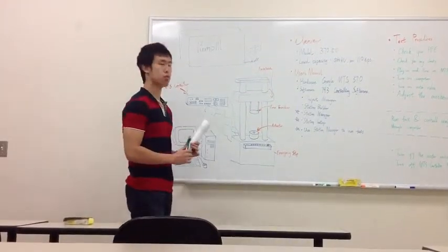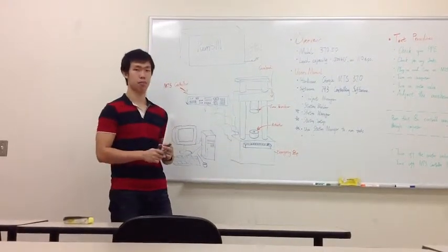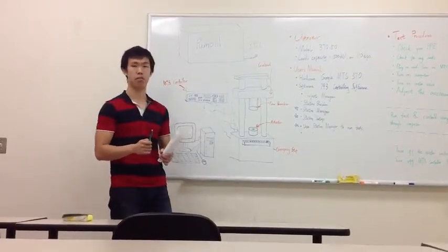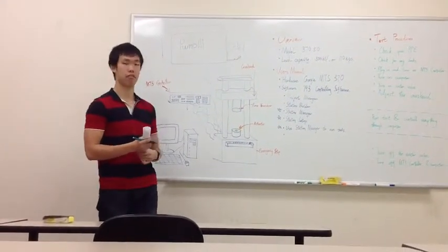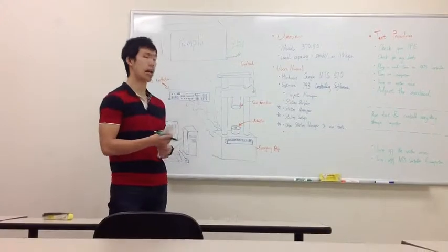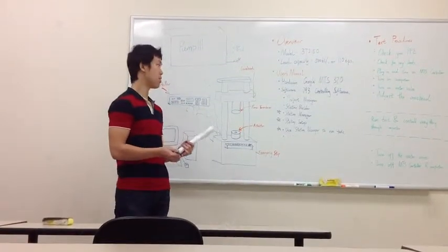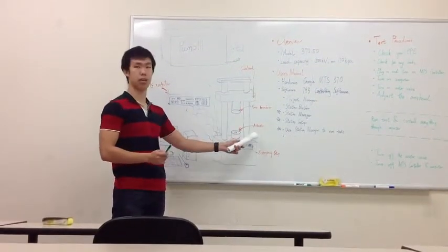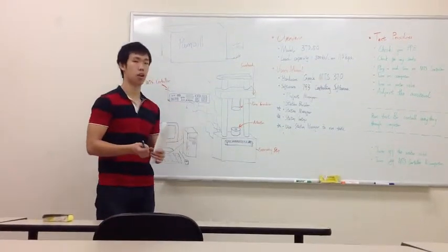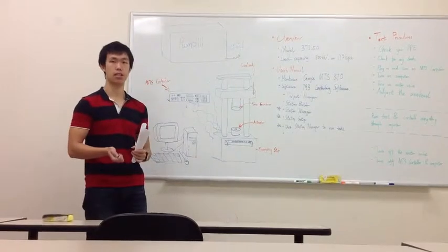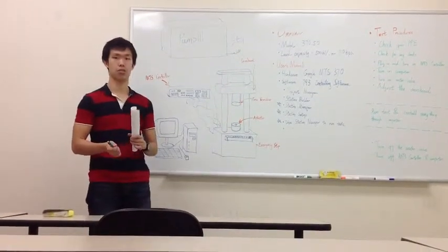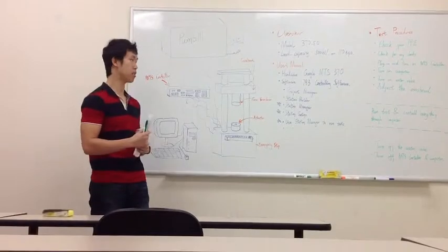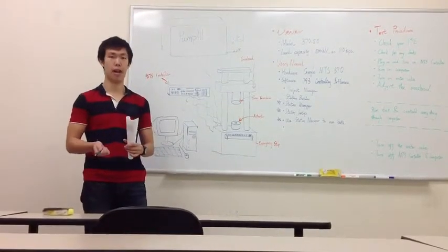Just some overview. The model number of this MTS is 370.50, which has a load capacity of 500 kN or 110 kips. That means both the force transducer and the actuator will have a maximum load capacity with 110 kips in both tension and compression. So before you run your test, you need to do some calculation and make sure that your test will not go over the load capacity.